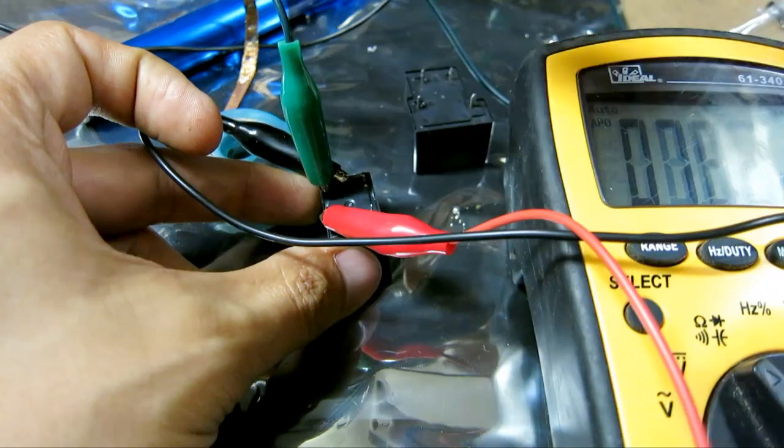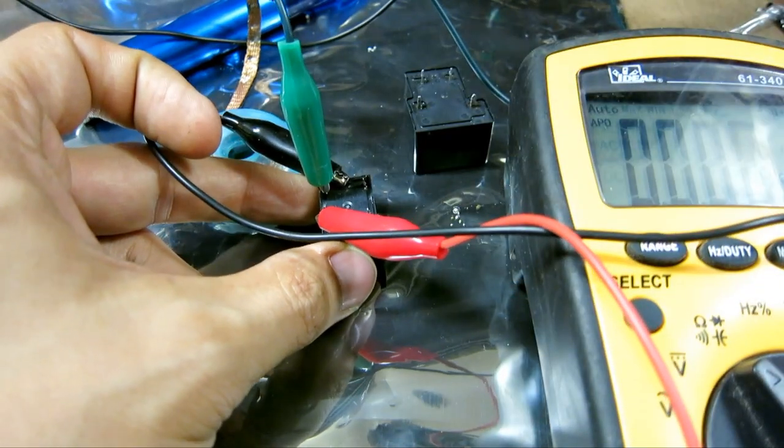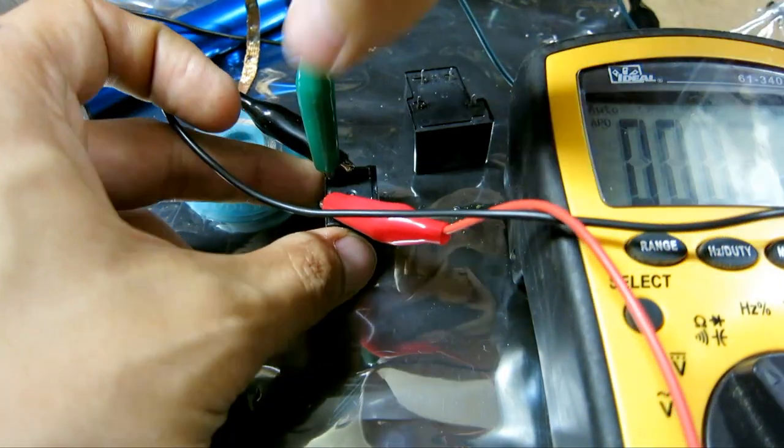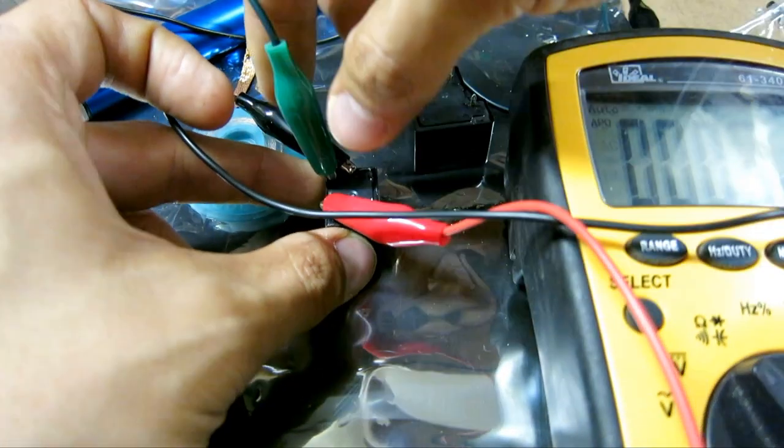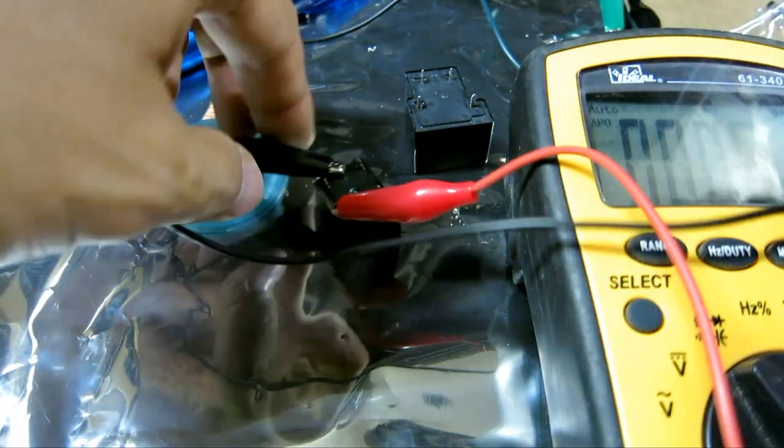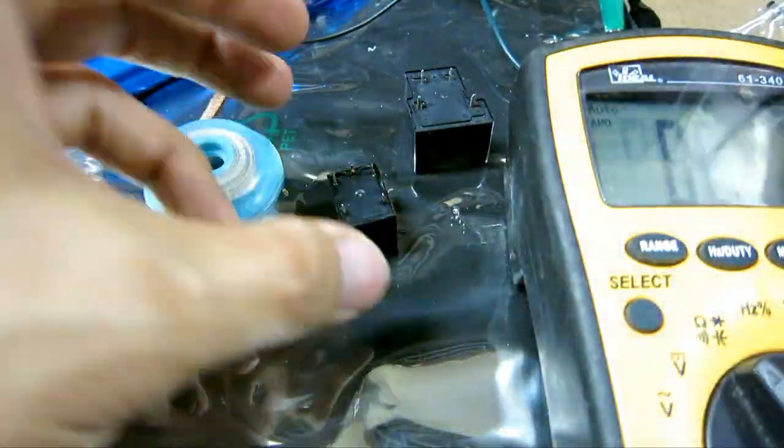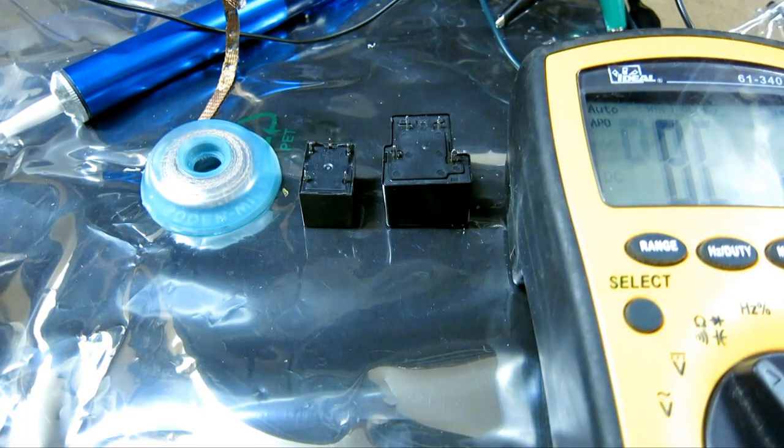And this also closes too, and I get zero ohms. And then as you can hear it click, which means it clicks over to this side. And this side is also shorted. So technically, these two relays are good, which means that maybe the board is bad to begin with.